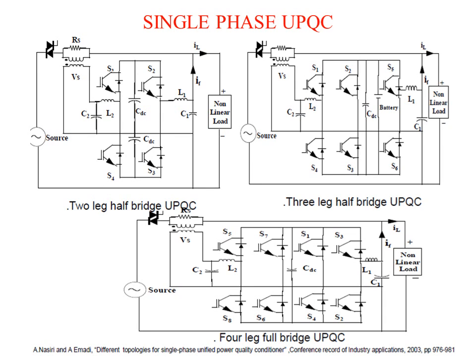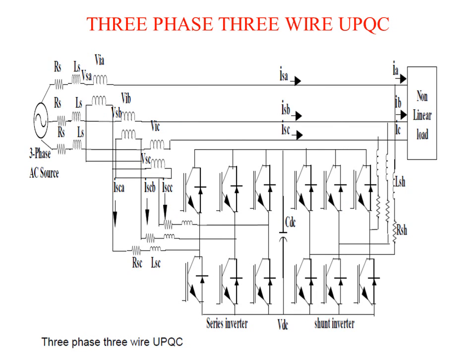These are the configurations of UPQC: single-phase UPQC includes two-leg half-bridge UPQC, three-leg half-bridge UPQC, four-leg full-bridge UPQC; then three-phase three-wire UPQC, and three-phase four-wire UPQC. There are also hybrid types of UPQC. The basic operating principle remains constant — there are always two back-to-back connected converters. Depending upon the supply system, whether single phase or three phase, we can have different configurations including single-phase half-bridge, full-bridge, two-leg, three-leg, three-phase three-wire, and three-phase four-wire.